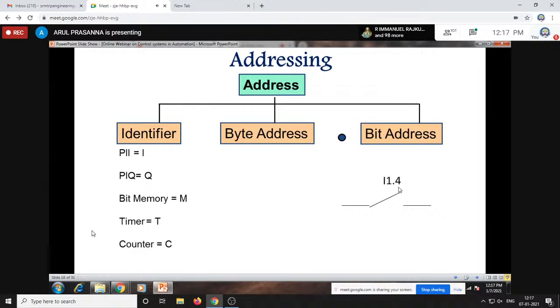While programming, you must define how many input and output terminals the hardware PLC is going to have. Only then can we make use of the inputs and outputs you have mentioned in your software programming when it is downloaded to your hardware PLC. Similarly, outputs might have addresses from 0.0 up to some 256 bytes. This is for Siemens type PLCs. Siemens uses the identifiers I and Q.